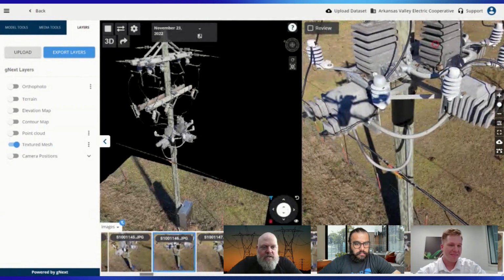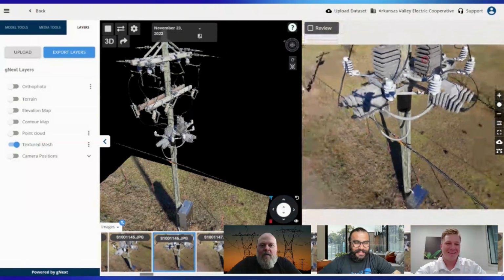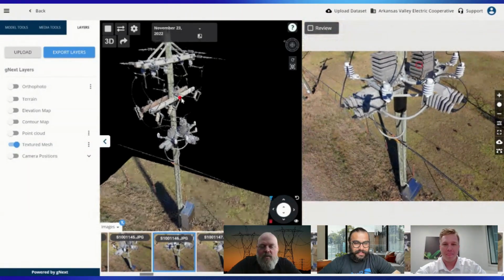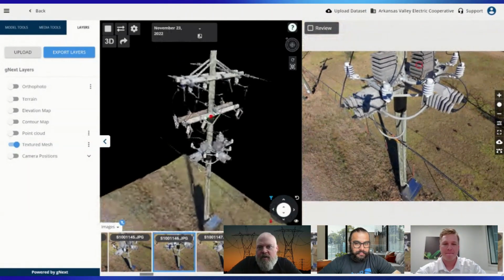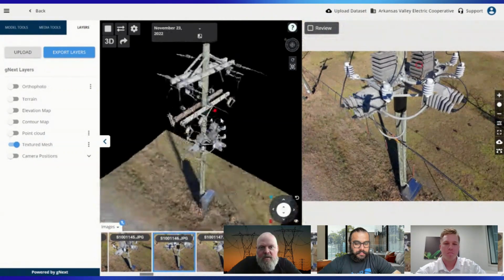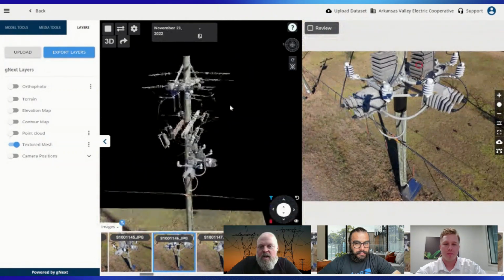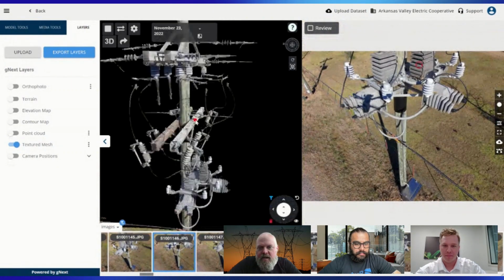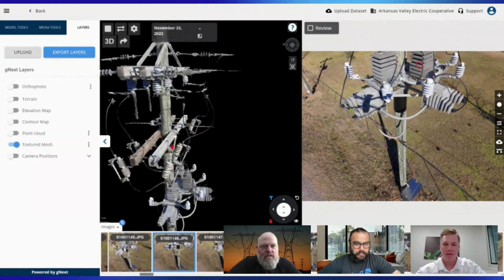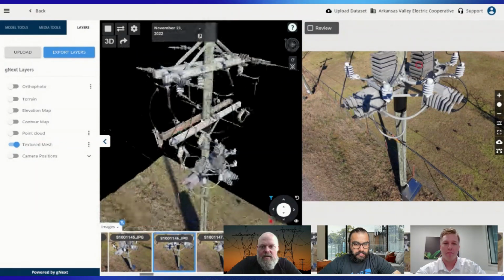Yeah, we got squirrel guards on those lightning arresters, and they're in place and healthy. This is a pretty cool model because with it and the 3D scan you can clearly see the status of the recloser, that it's online, with your line and source side disconnects closed and your bypasses open. Everything's good. I was pretty impressed by this model.